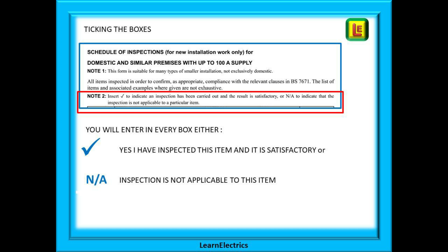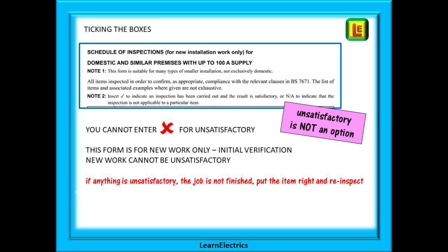You will enter either a tick to say 'yes, I have inspected this item and it is satisfactory,' or you will enter N/A to say that inspection is not applicable to this item — this item does not apply to this circuit. This is very important: you cannot enter an X for unsatisfactory. This form, the schedule of inspections, is for new work only — initial verification — and new work cannot be unsatisfactory.